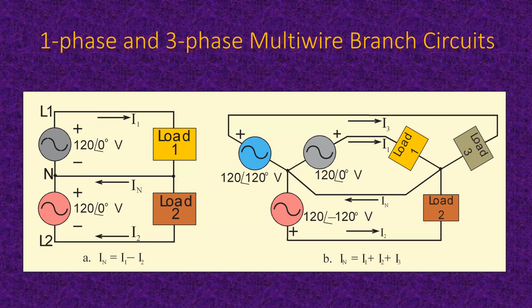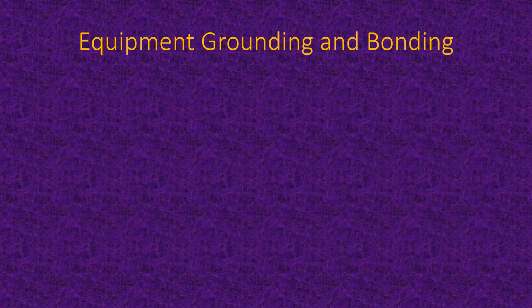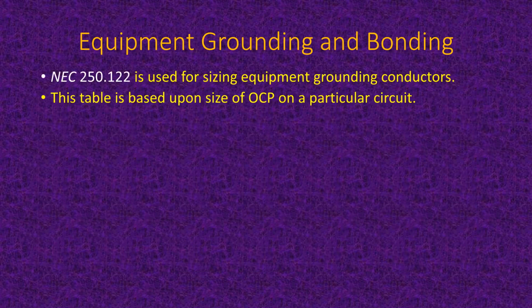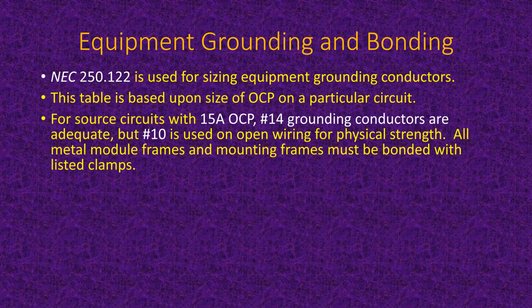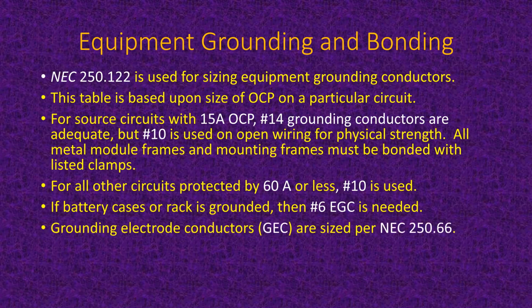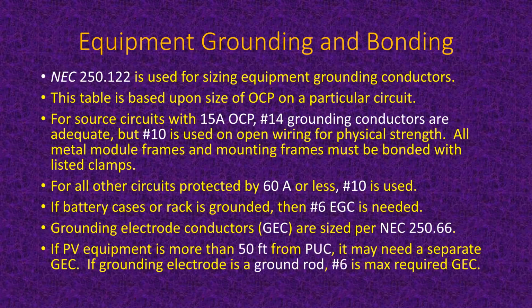Same thing if you've got a 3-phase system in a bigger building. If you take one load that's important, you've got to take the other 2 on that same circuit to balance the loads on the neutral. Just some thoughts there, and something that's not a major, well, it is a concern. When you do create a second panel, you need to make sure that you move every load that has a common neutral along with that common neutral into the new panel. Equipment grounding and bonding: again, all the rules, NEC 250, you just follow the National Electrical Code on the grounding for equipment grounding conductors and grounding electrode conductors. Rules are all the same.